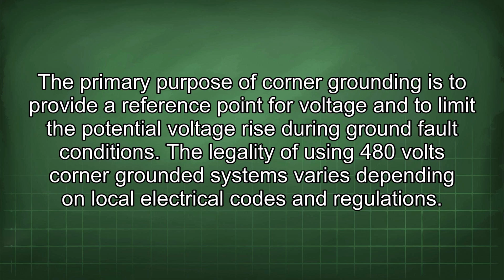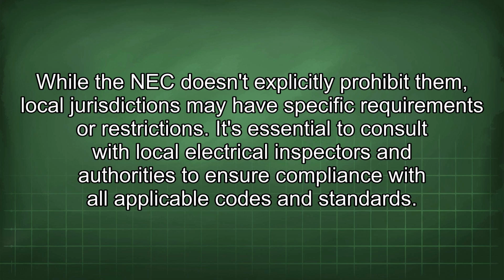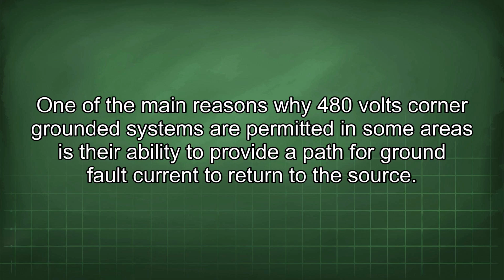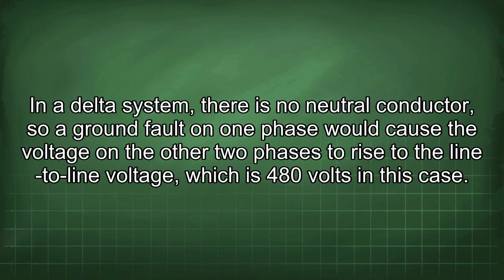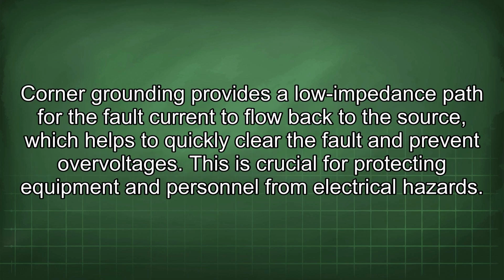The legality of using 480 volts corner-grounded systems varies depending on local electrical codes and regulations. While the NEC doesn't explicitly prohibit them, local jurisdictions may have specific requirements or restrictions. It's essential to consult with local electrical inspectors and authorities to ensure compliance with all applicable codes and standards. One of the main reasons why 480 volts corner-grounded systems are permitted in some areas is their ability to provide a path for ground fault current to return to the source. In a delta system, there is no neutral conductor, so a ground fault on one phase would cause the voltage in the other two phases to rise to the line-to-line voltage, which is 480 volts in this case. Corner grounding provides a low impedance path for the fault current to flow back to the source, which helps to quickly clear the fault and prevent overvoltages. This is crucial for protecting equipment and personnel from electrical hazards.